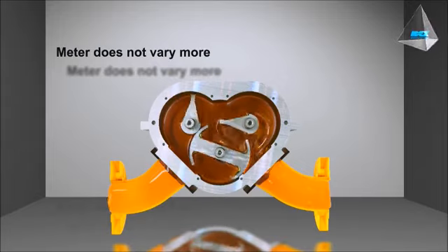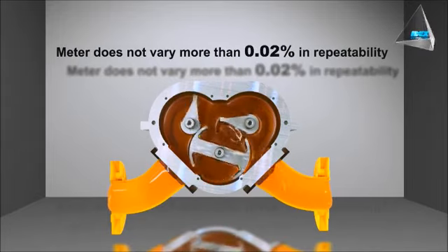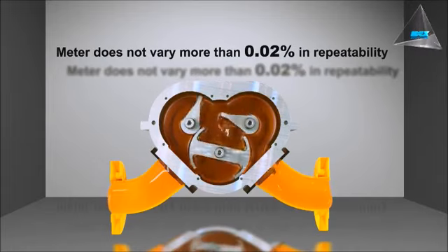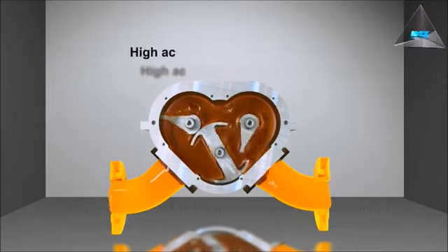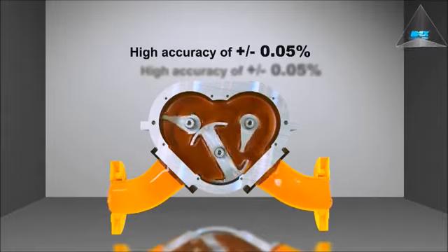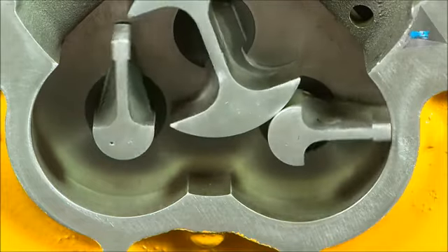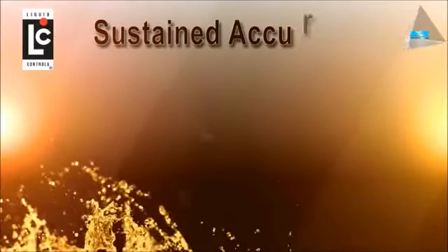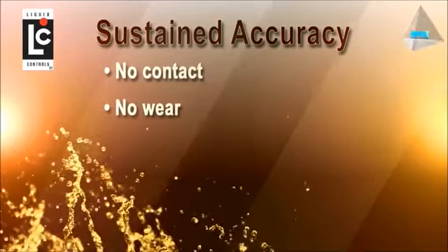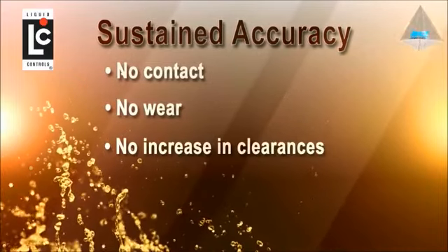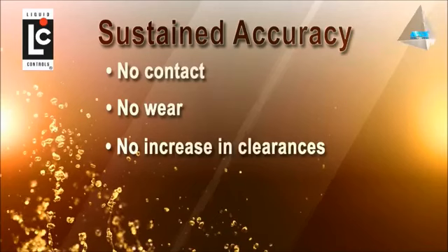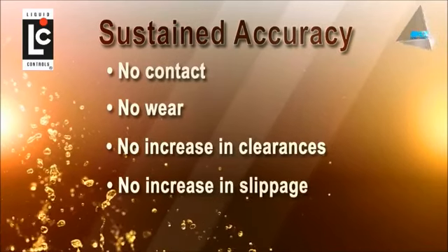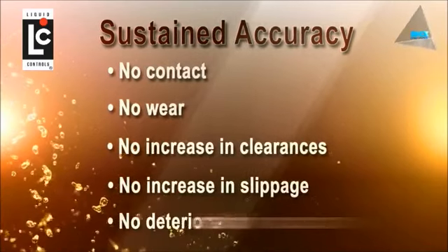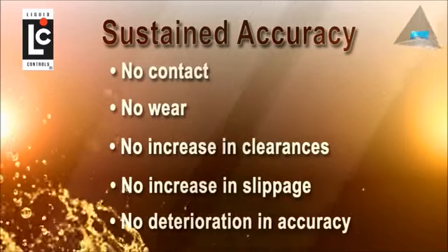With all other conditions being constant, the LC meter does not vary more than 0.02% in repeatability over the entire range of the flow and has a very high accuracy of plus or minus 0.05%. There is no metal-to-metal contact within the metering element, and no contact means no wear. No wear means no increase in clearances. No increase in clearances means no increase in slippage. And no increase in slippage means no deterioration in accuracy.